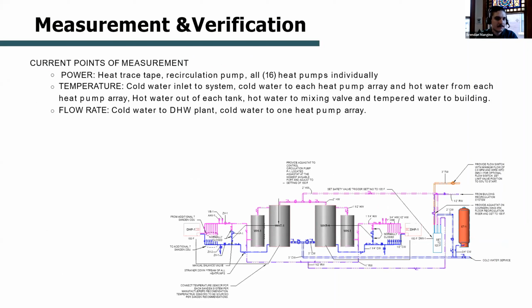So we're taking data measurement at the heat trace tape, recirculation pump, and all 16 heat pumps individually, and that's for the power measurement. We're also taking temperature measurements at the cold water inlet to the system, cold water to each heat pump array, hot water from each heat pump array, hot water out of each tank, hot water to the mixing valve, and tempered water to the building. So all of that data would be really useful for me as the design engineer, but some of that data will also be useful to get the effective COP of the system. And lastly, we have flow rate, cold water to the domestic hot water plant, and cold water to one of the heat pump arrays.